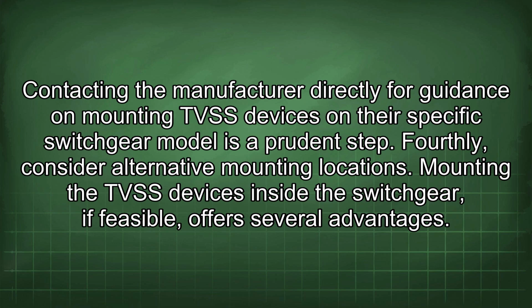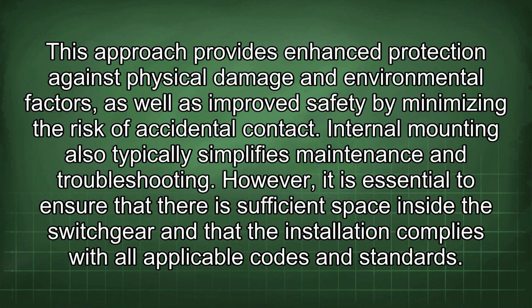Fourthly, consider alternative mounting locations. Mounting the TVSS devices inside the switchgear, if feasible, offers several advantages. This approach provides enhanced protection against physical damage and environmental factors, as well as improved safety by minimizing the risk of accidental contact. Internal mounting also typically simplifies maintenance and troubleshooting. However, it is essential to ensure that there is sufficient space inside the switchgear and that the installation complies with all applicable codes and standards.